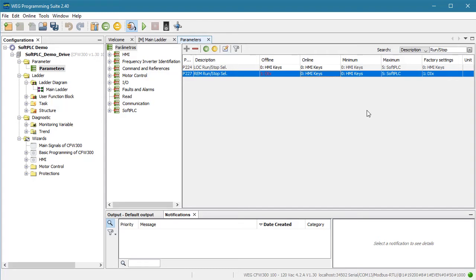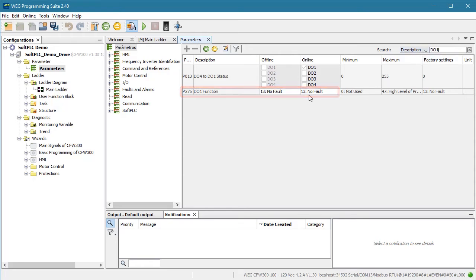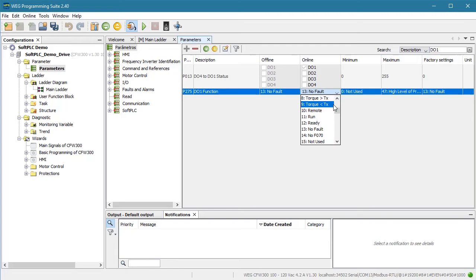Now, what about digital output 1? We want to use it to turn the indicator on. Does the drive have any default plans for it? Search on DO1. Yep, parameter 275 says the drive is planning to use this to indicate a no fault condition. Now this one we do have to change. We can't have two different functions trying to control a single output. The drive will let you do it, but you would never know which one is controlling the output. So let's tell the drive that for our demo only the soft PLC will be controlling this output.